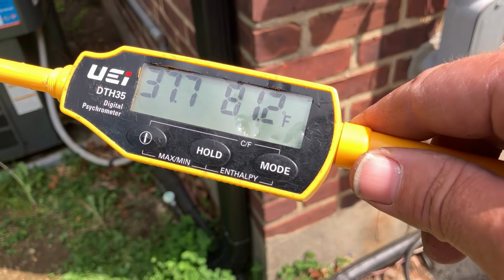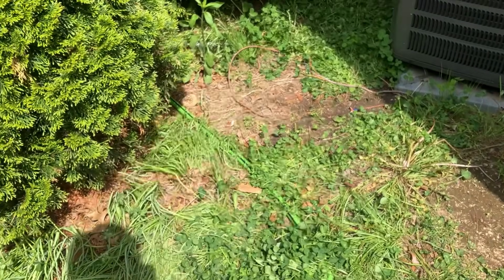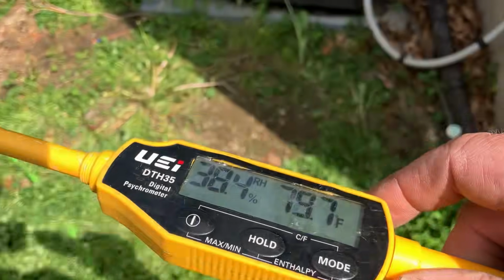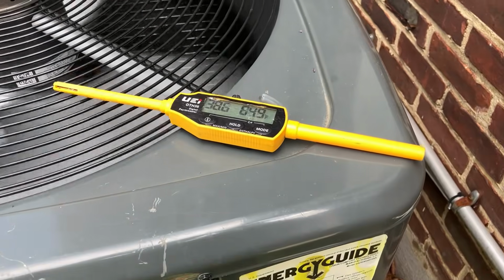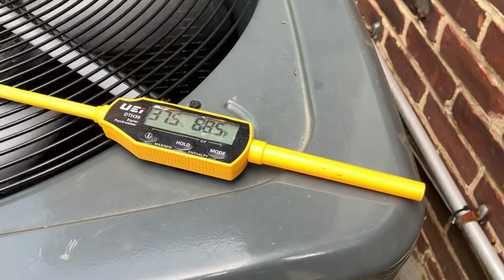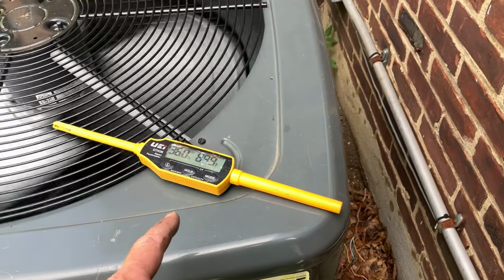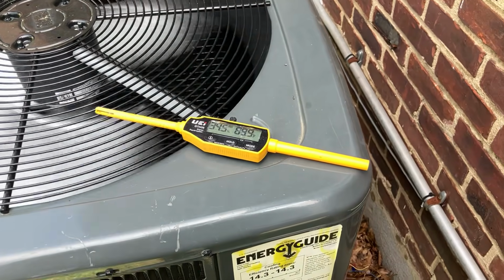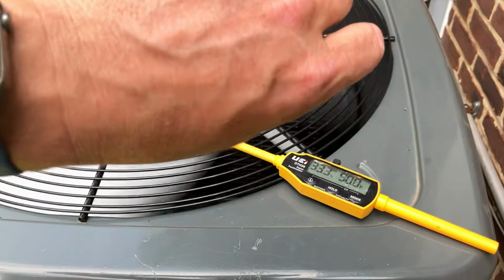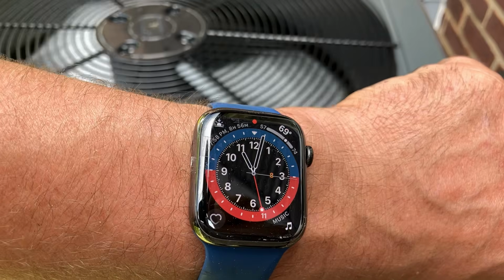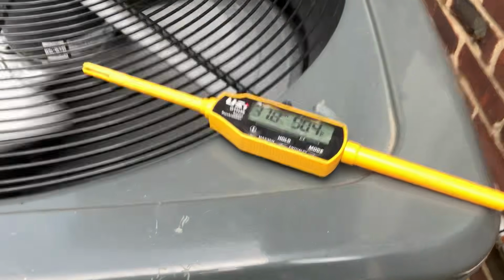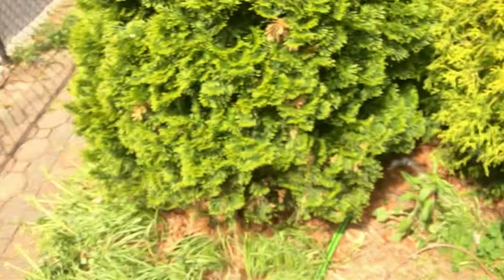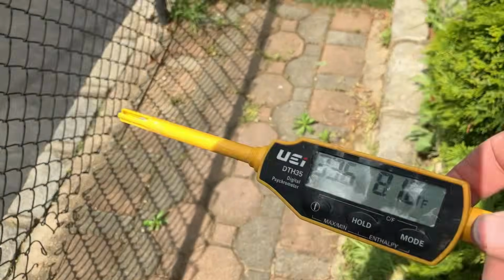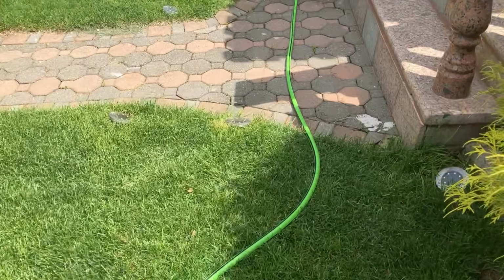All right, ambient temperature. Spin this around a few times. 80 degrees, wow. Discharge temperature. I don't check refrigerant on a system unless I suspect there's a problem with the refrigeration cycle. We're at 90 degrees. Well, according to my Apple Watch, ambient is 69, but my digital psychrometer, I hope she ain't lying. Spin around a few more times here. Oh, it's 81 degrees here. Let's check our return and supply temperatures.